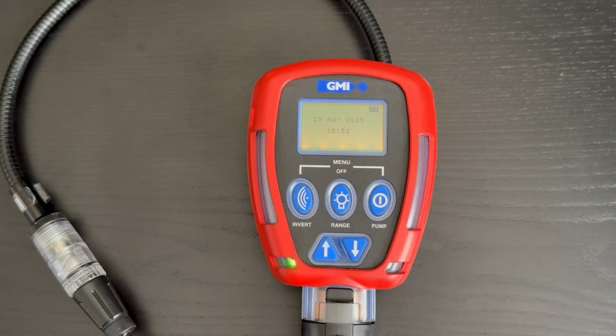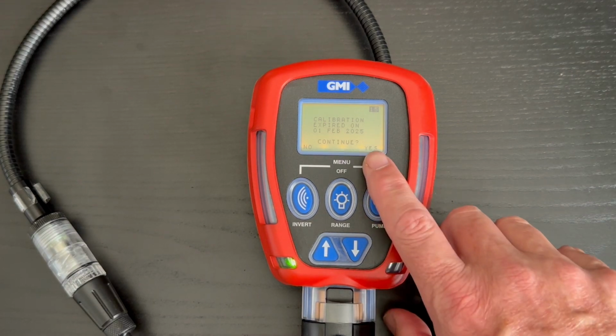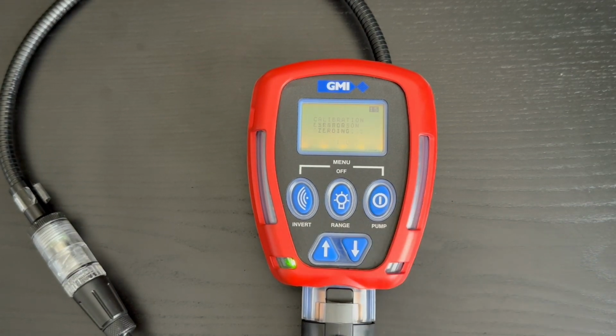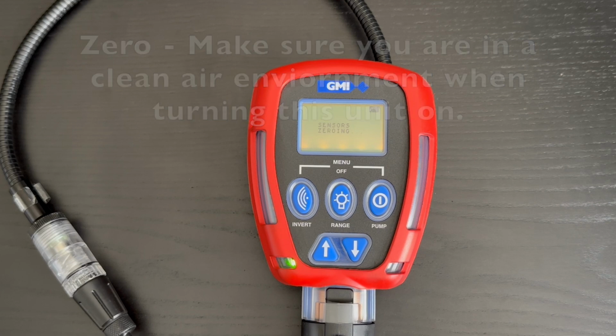And now it's going to do a countdown where it's booting up, heating up the LEL sensors, checking the EEPROMs, giving you calibration dates. You'll notice that this one is out of calibration date. We're going to do a calibration on this in the next series of videos. But I am going to say yes, soft arrow key, yes to continue. It does a quick 0 on some sensors, and then we'll go into what we call real-time readings.